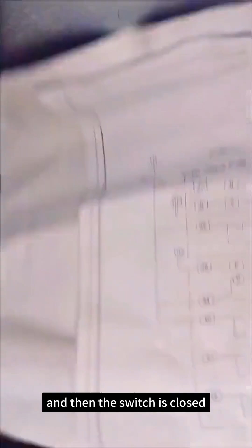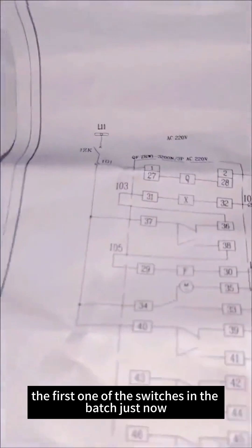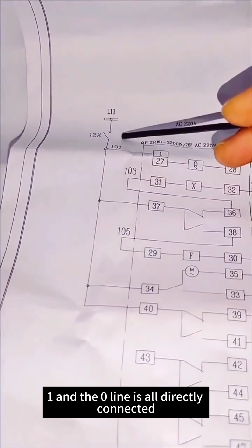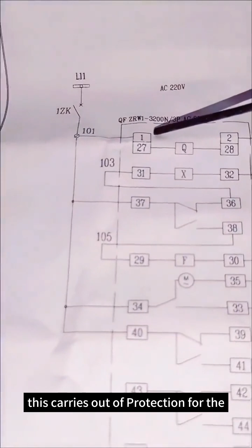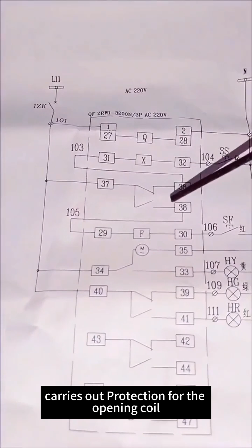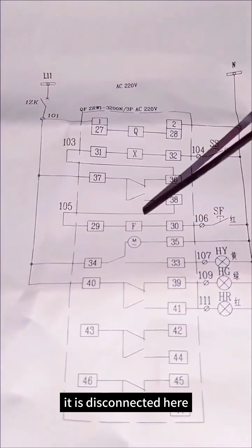First, our L connects to the power supply side of the transformer, and when the switch closes, the first terminal supplies the functional panel, with the neutral line directly connected. Terminal 37 provides protection for the closing coil, and 37-38 provides protection for the opening coil. Then after the motor at 34-35 stores energy, it's disconnected here.